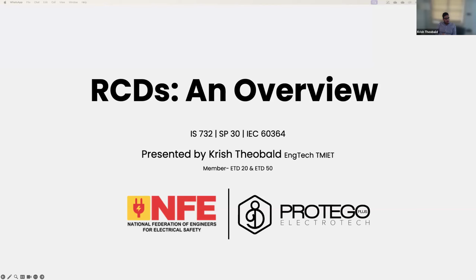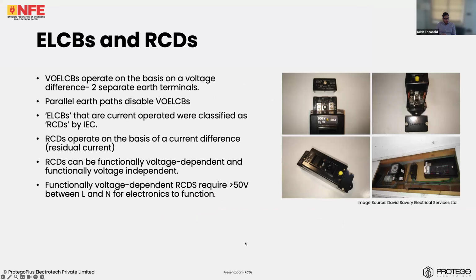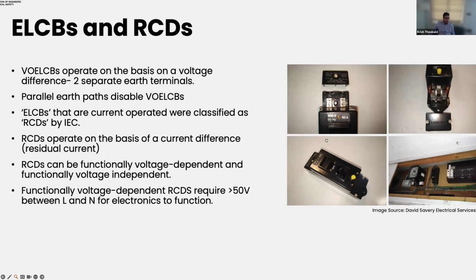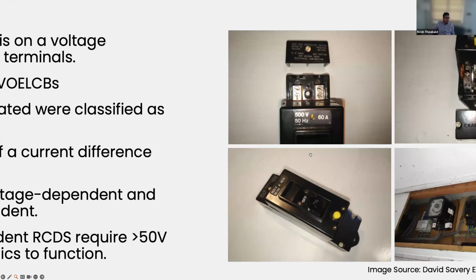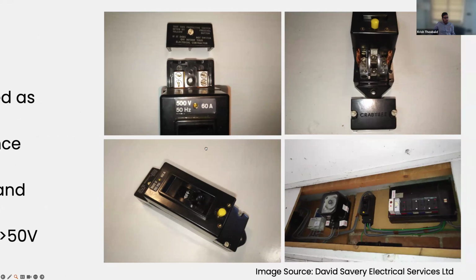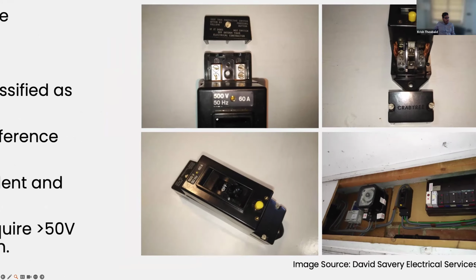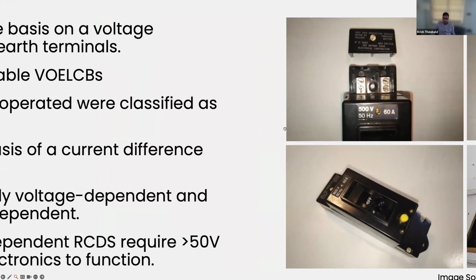Gerard will be the main speaker because he's an expert on this subject, but I'll give you a brief introduction. I want to illustrate that ELCBs are not available in the market. It's very important that we recognize this because very often, when we've gone to so many places across the country doing our events, everywhere the term ELCB is being used instead of the term RCD. I want to illustrate that actually we are not using ELCBs anywhere. This picture shows you what an ELCB actually looks like. We don't use anything like this today. There is an incoming line and neutral, and there is an earth conductor also in the circuit breaker. This is a very old device that is no longer used in the market today.